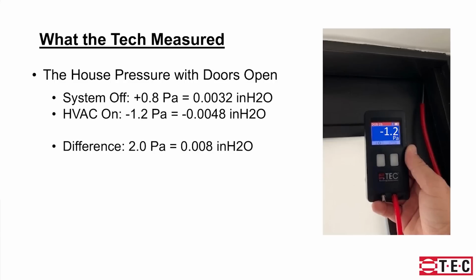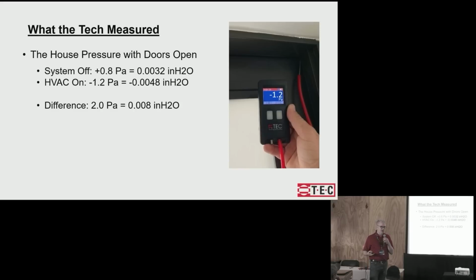Okay, but in this case, here's what the technician found. With the system off, he measured 0.8 pascals, a tiny pressure, 0.0032 inches of water. And then with the HVAC system on, it jumped from plus 0.8 to minus 1.2. So the amount that it changed was 2 pascals, or 0.008 inches of water. Okay, 0.008, does that matter? That's a tiny pressure. We're going to talk about why that matters and what he found.